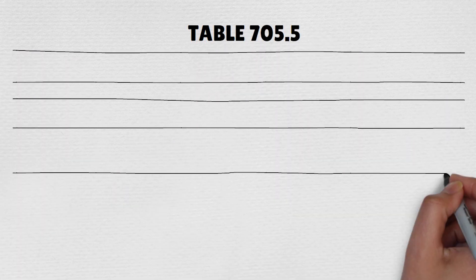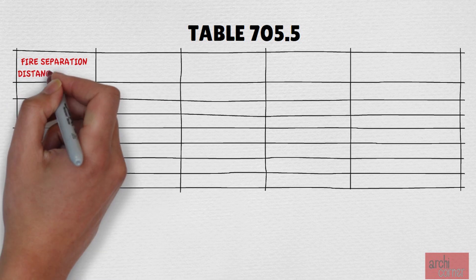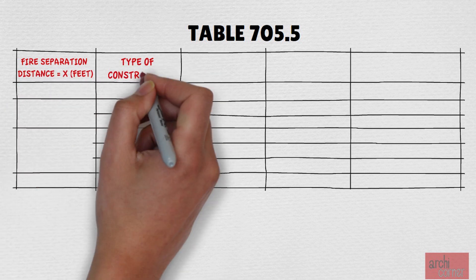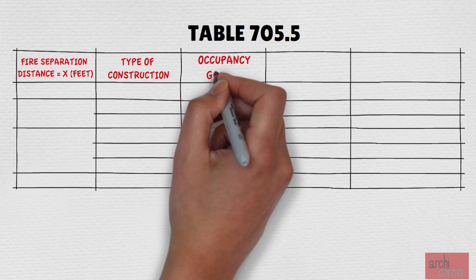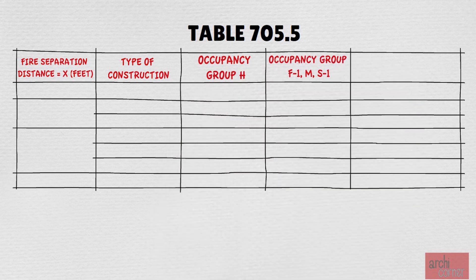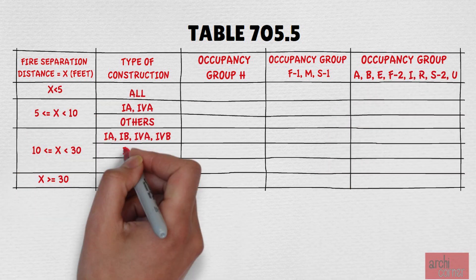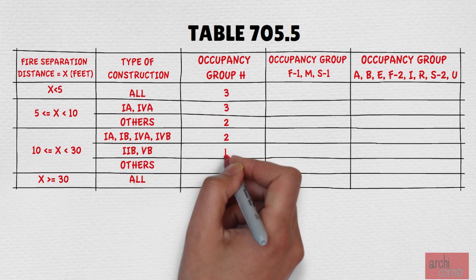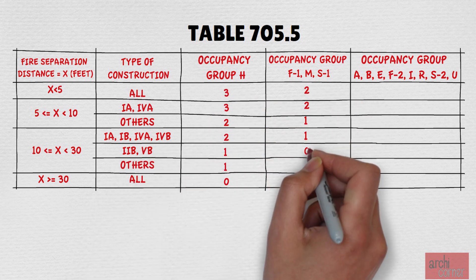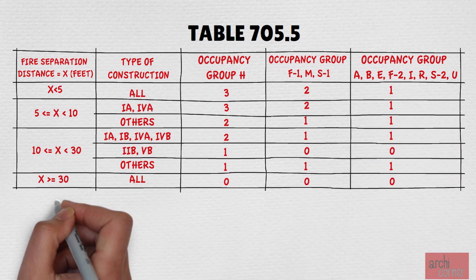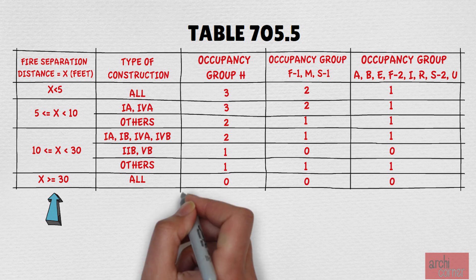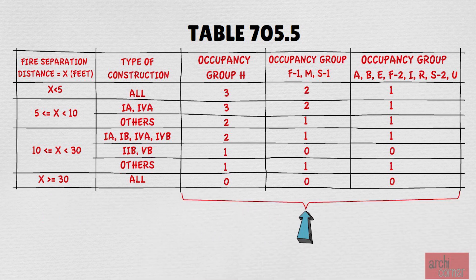Separation requirements can be found in IBC Section 705 and Table 705.5, which notes the required fire resistance rating required for walls based on their proximity to either the actual property line or the assumed property line — I will discuss this assumed property line in a minute. Be aware that there are a few footnotes not shown on this table, so be sure to look at the IBC for the full table. This chart is relatively straightforward: the column on the left notes the distances between the building and the property line, and the other columns note the fire rating required, which depends on the type of construction and occupancy group.